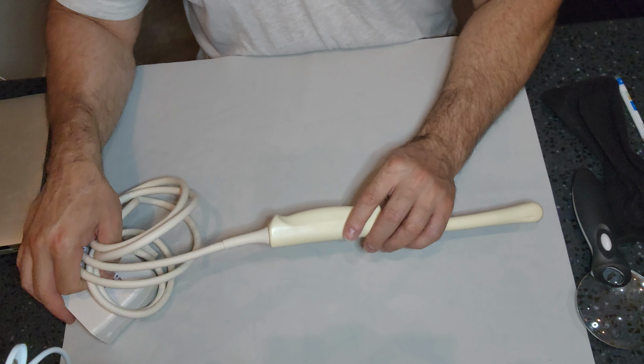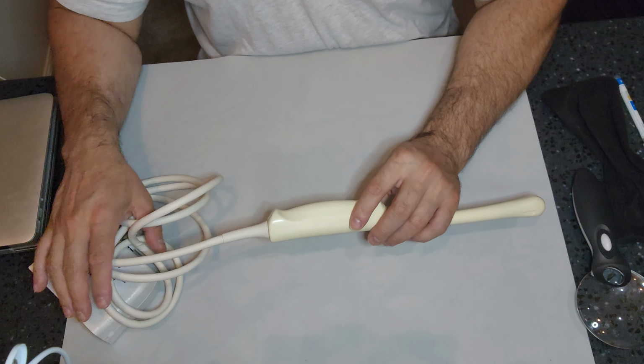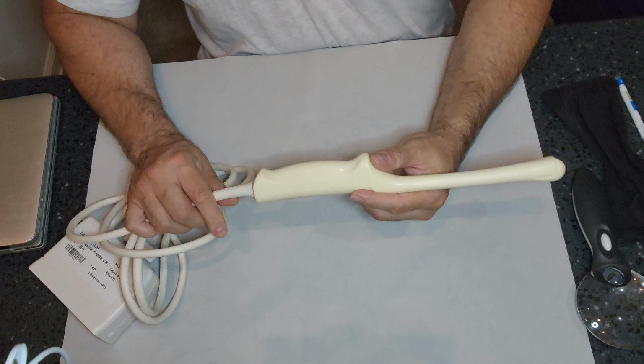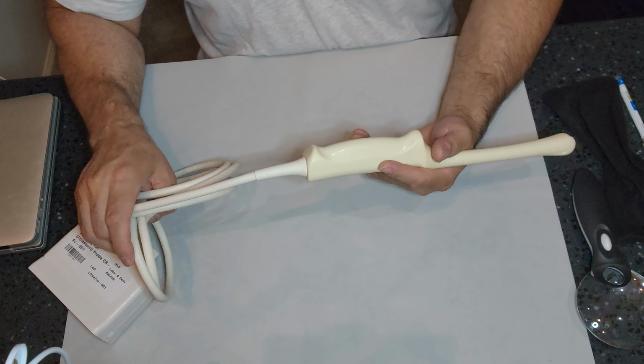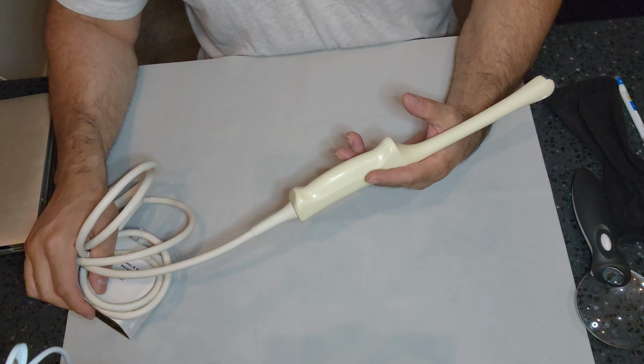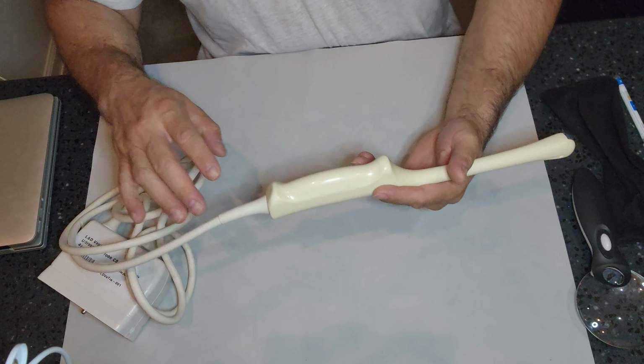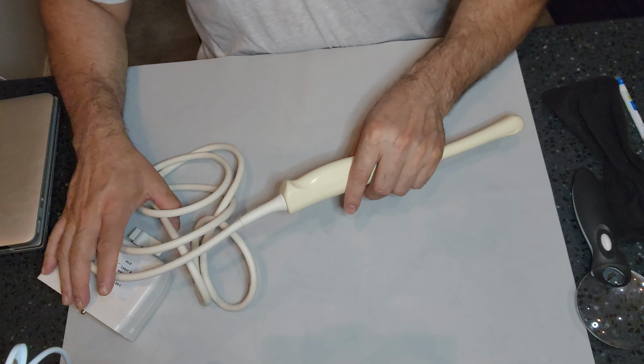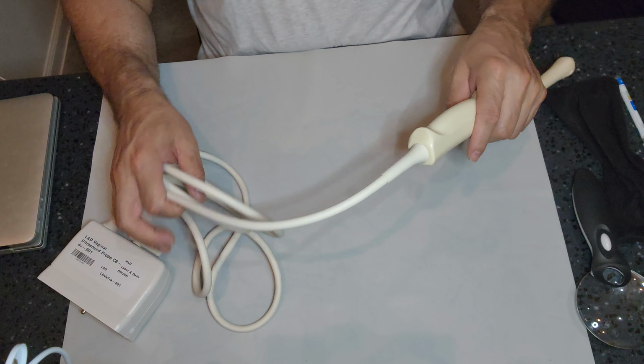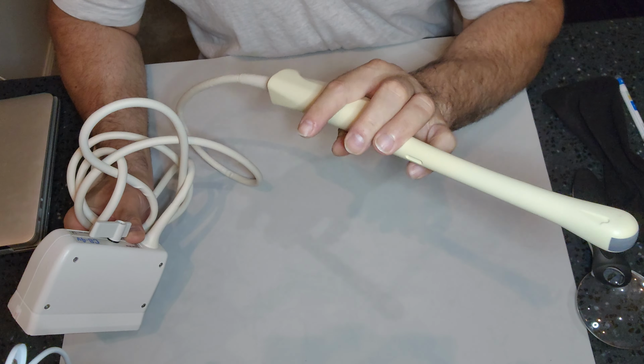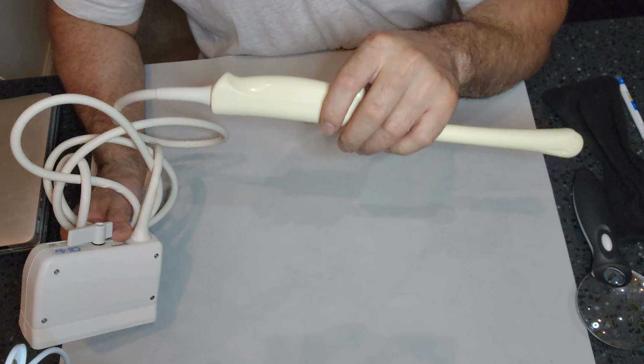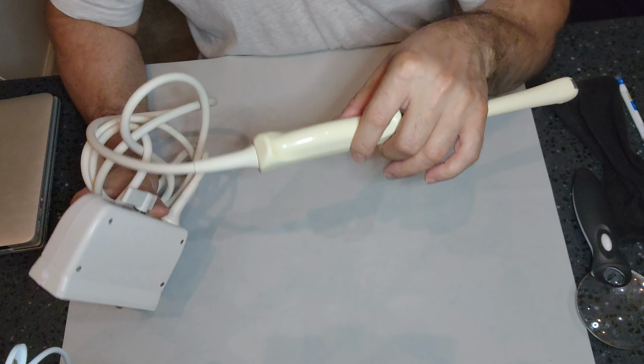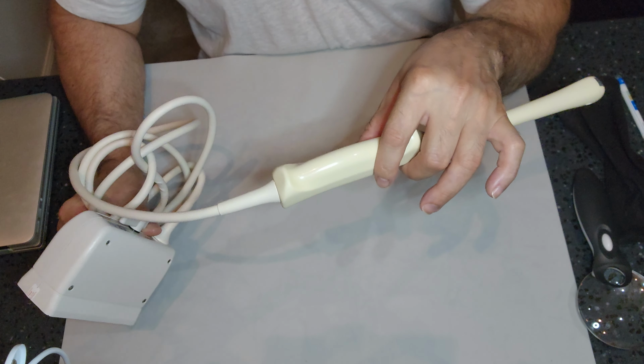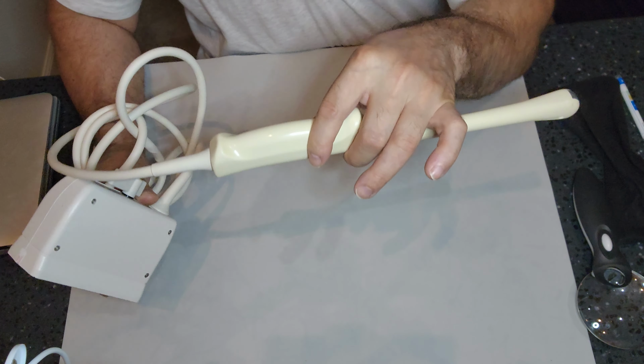If you're using an APR, I gave the name, automatic probe reprocessor. All right, which one are you using? There are different ones out in the market. So again, how are we placing that in there? If there are any connectors that go to it, some of the automatic probe reprocessors require the box to be plugged in so that you can leak test the probe, because you have to make sure that there's no damage in there. So some probes require leak testing. Again, look at the IFU. Does it require a leak test? If you're leak testing it, okay, that happens while it's in the APR.